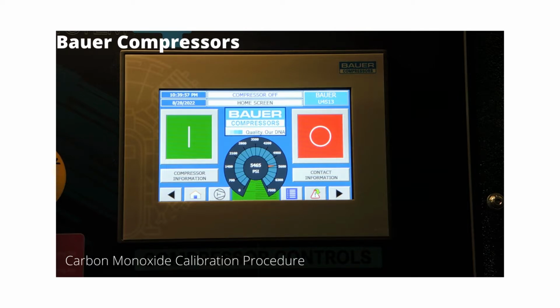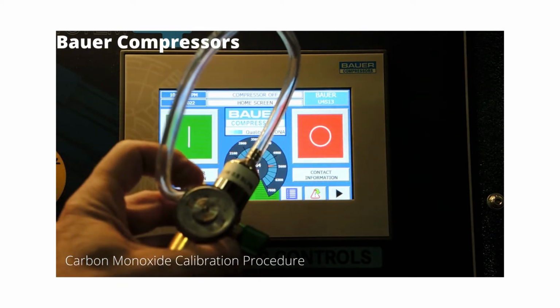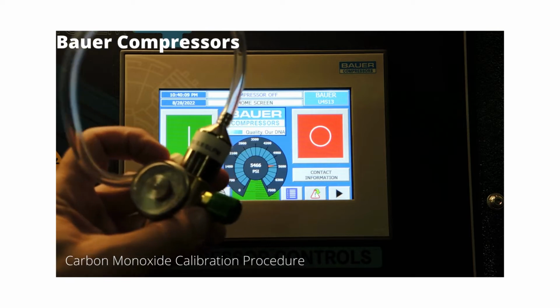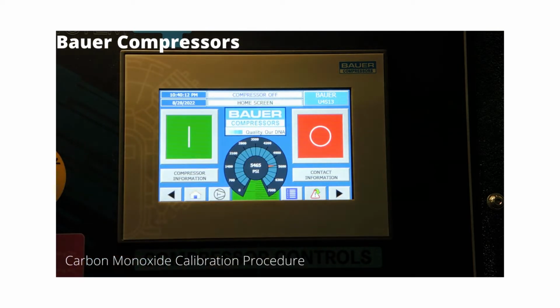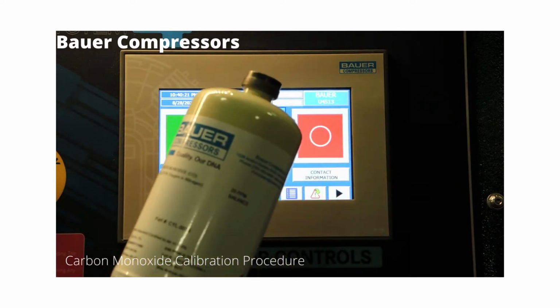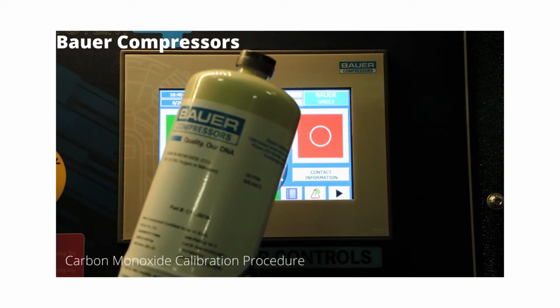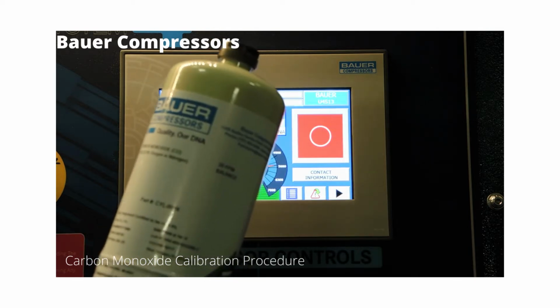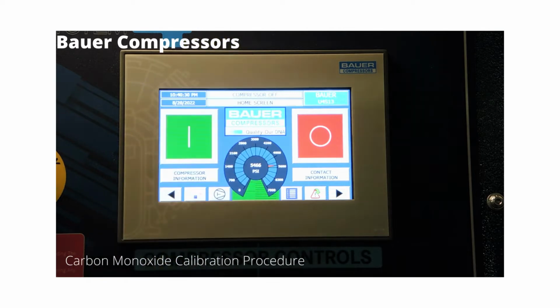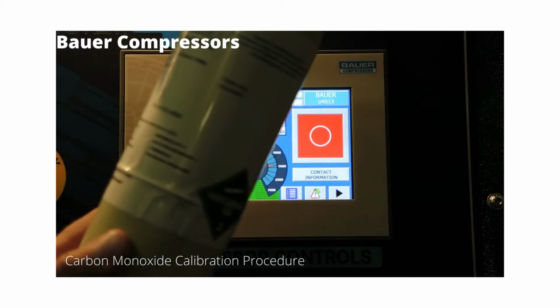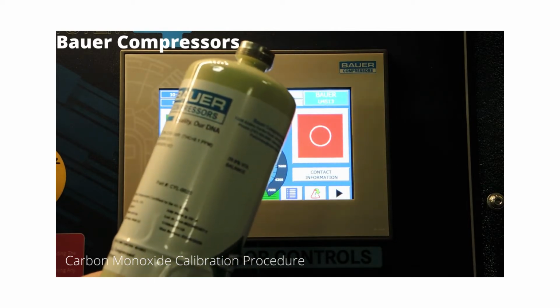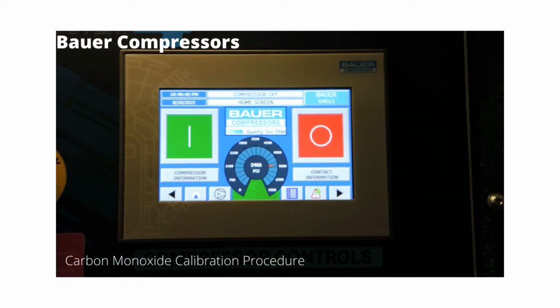do the calibration. Okay, so this is the home screen you'll see. You're going to want to make sure that you have a regulator. There's multiple regulators available, but this is the regulator that has to be used on this CO system. It flows the proper pressure and flow. You're also going to want to make sure that you've got your test gases and that they're current and not expired. The test gas for the 20 part per million for the Bauer compressor systems is part number cylinder or CYL16, and the part number for the 0 test gas is CYL20. You're going to want to make sure you've got those before the calibration.